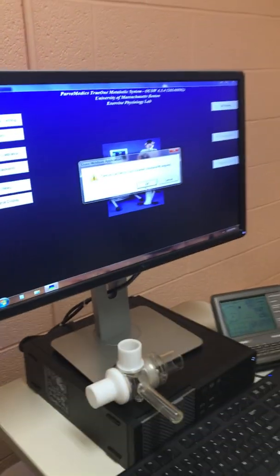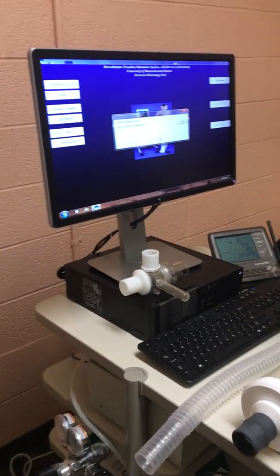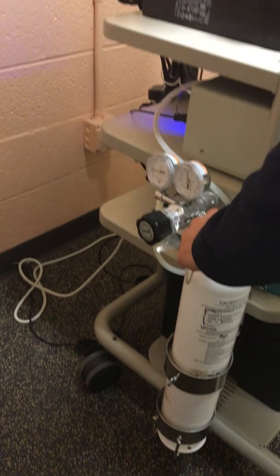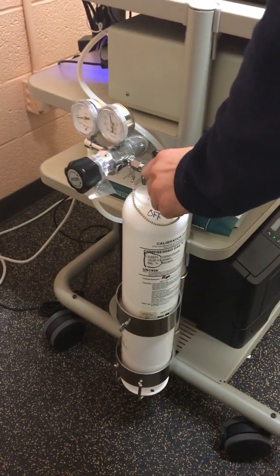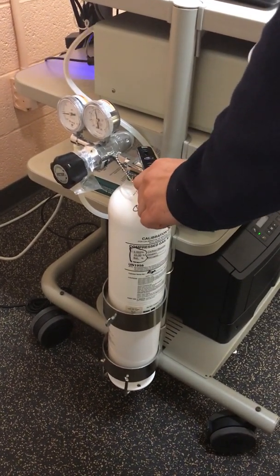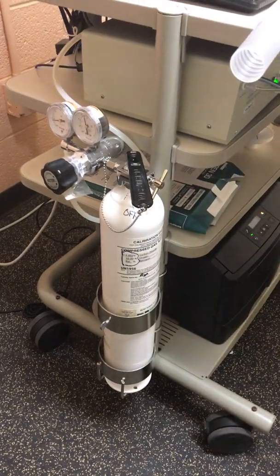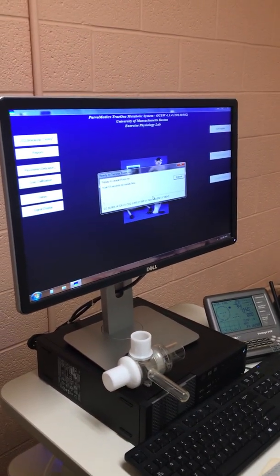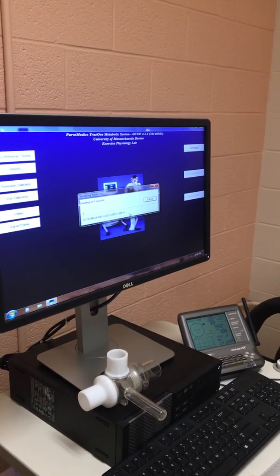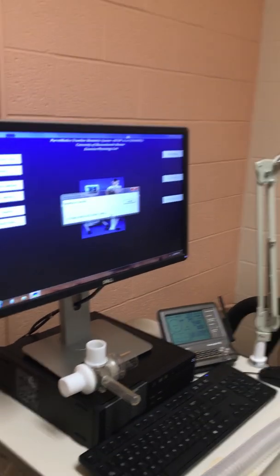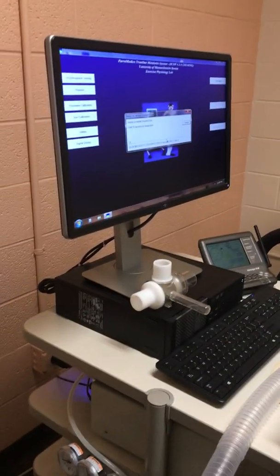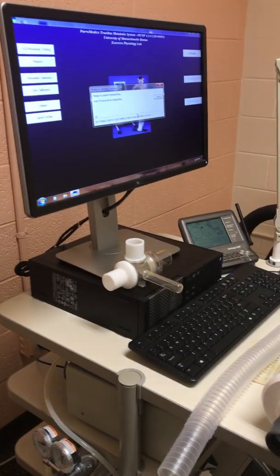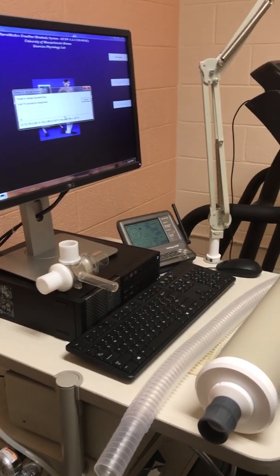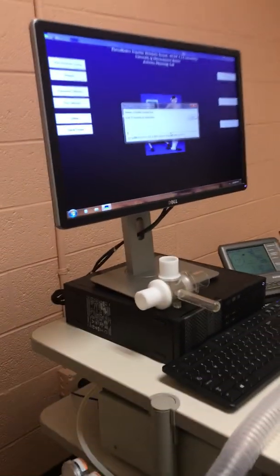And so after this, we're going to turn on our gas calibration to 3 psi. Be careful with that lever, it's pretty sensitive. And we're going to wait 15 seconds for this to calibrate. The computer is calibrating the gases in the room and the gases in our calibration tank. So we have nitrogen, carbon dioxide, and oxygen in the tank. And this is going to calibrate our system.